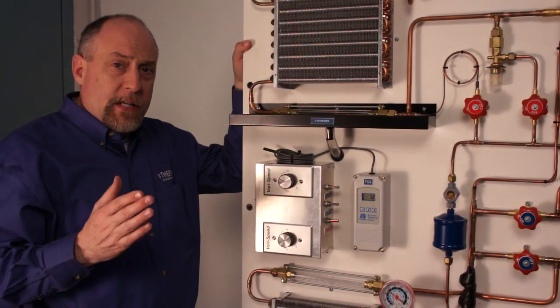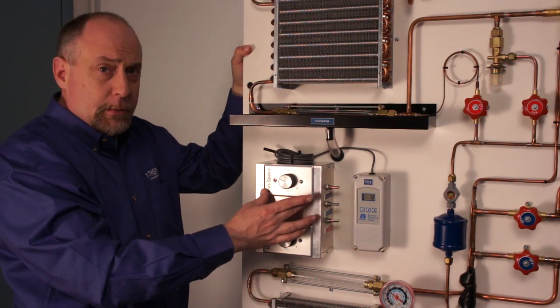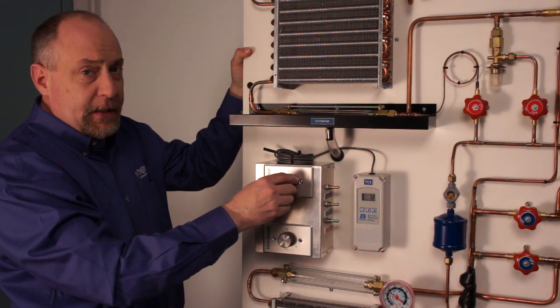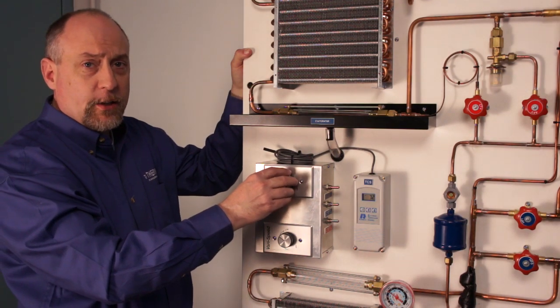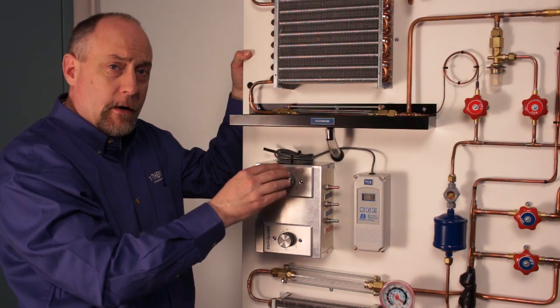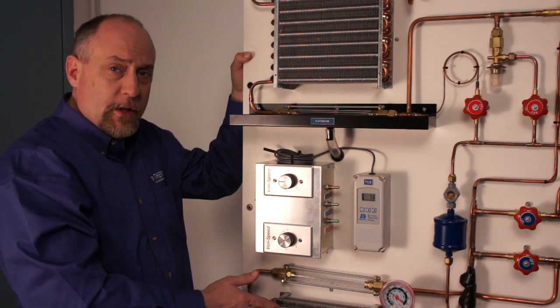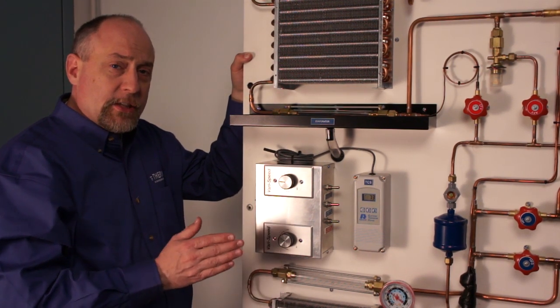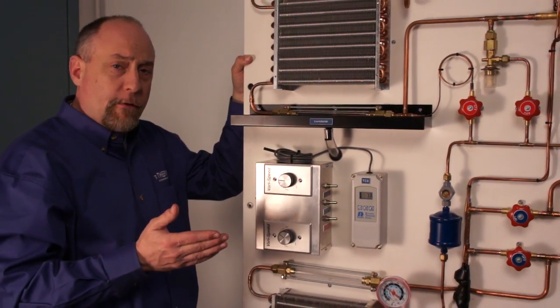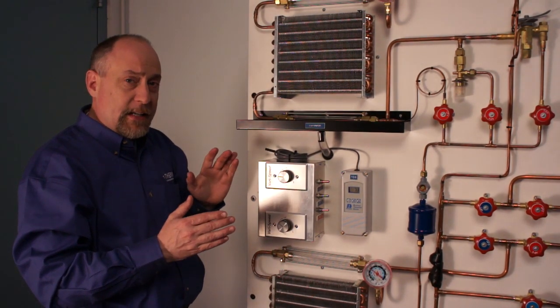One of the more important things for students to understand is how a system responds and changes to a load. By adding the variable speed fan controls, we allow you to demonstrate that. By simply adjusting the speed up or down — and you can hear the fan noise increasing considerably — we can change the amount of air and in turn the amount of load that goes across the evaporator, or change the amount of heat that's rejected in the condenser. This allows us to show the students what's going to happen if we have a dirty condenser, a dirty evaporator, high air flow, low air flow, and simulate a bunch of different conditions. The nice part is you can use it to predict behavior.